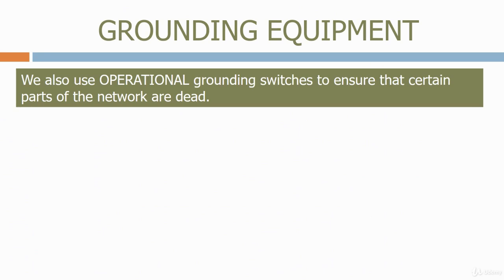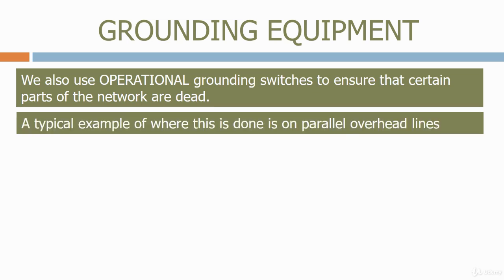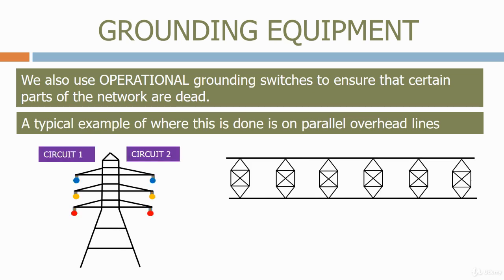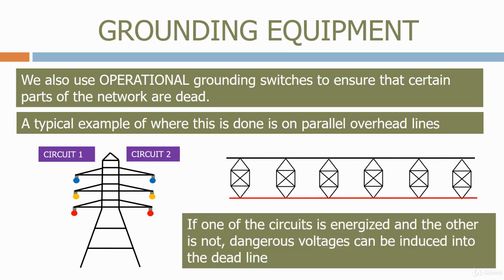We also use operational grounding switches to ensure that certain parts of the network are dead. A typical example of where this is done is on parallel overhead lines. Most overhead transmission towers have 2 parallel circuits. If one of the circuits is energized and the other is not, dangerous voltages can be induced into the dead line. To overcome this, ground switches are positioned at each end of the overhead line circuit.